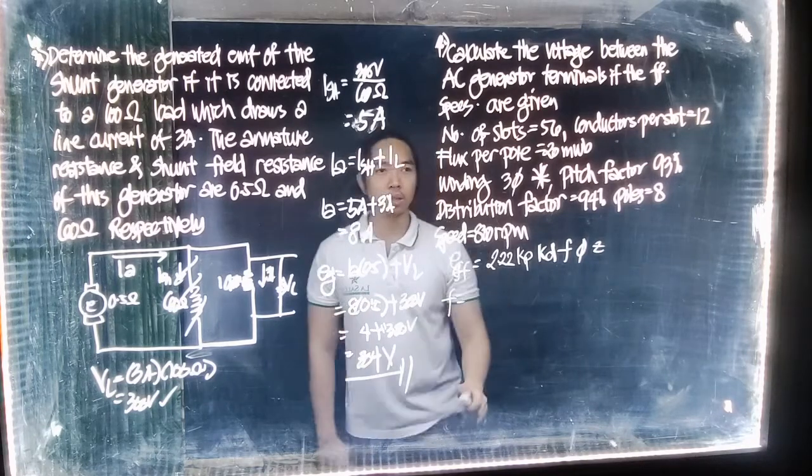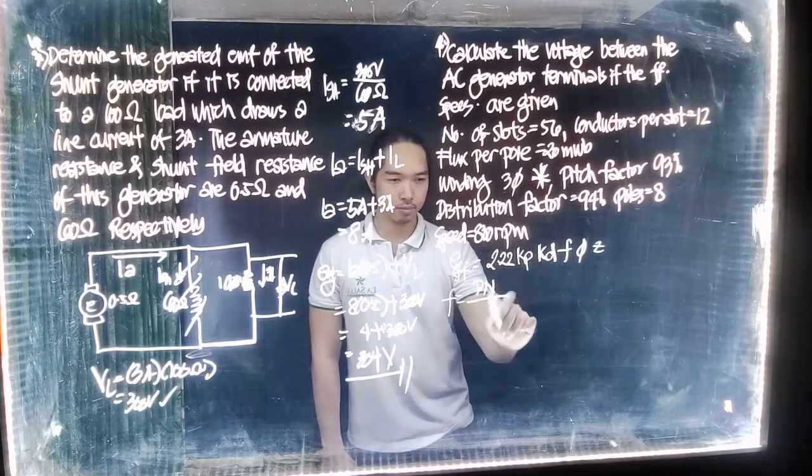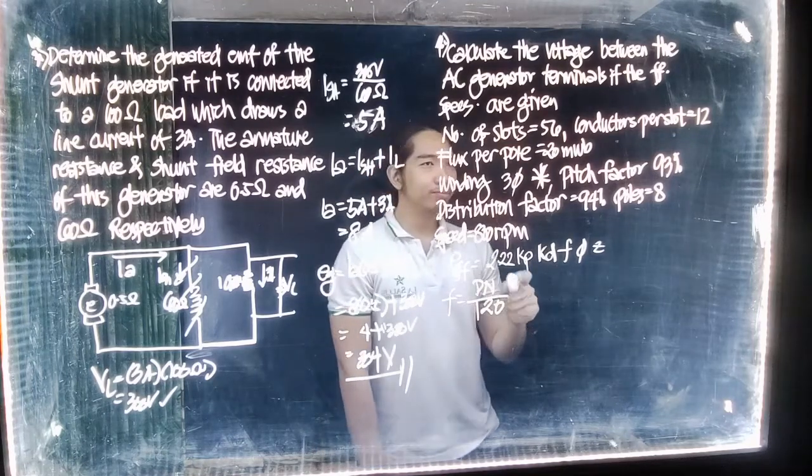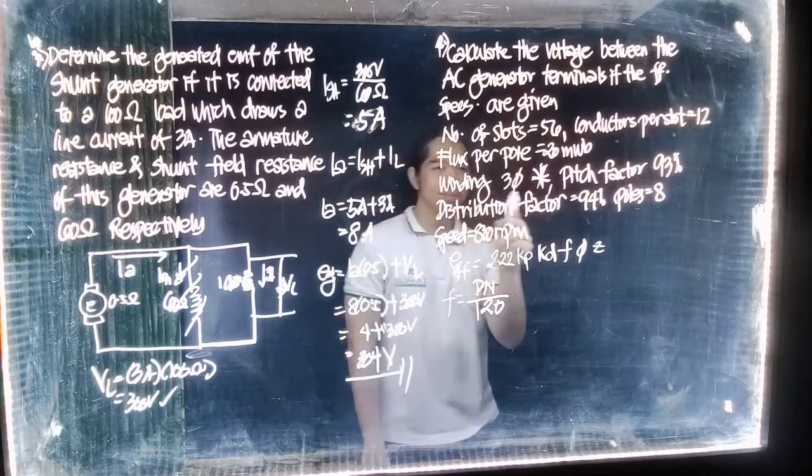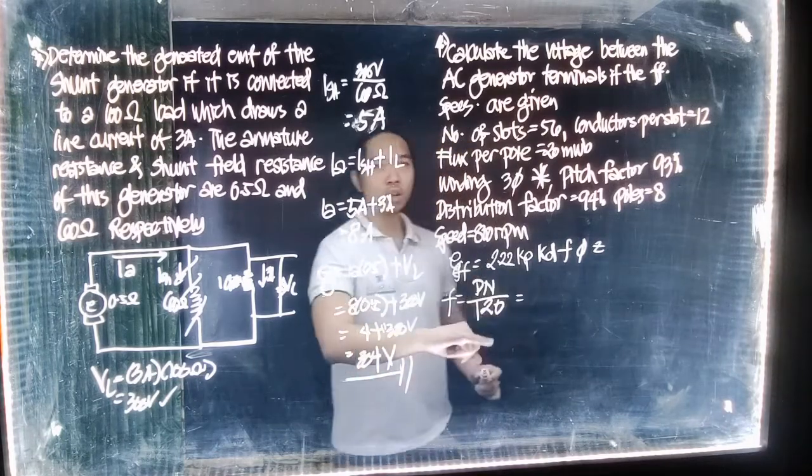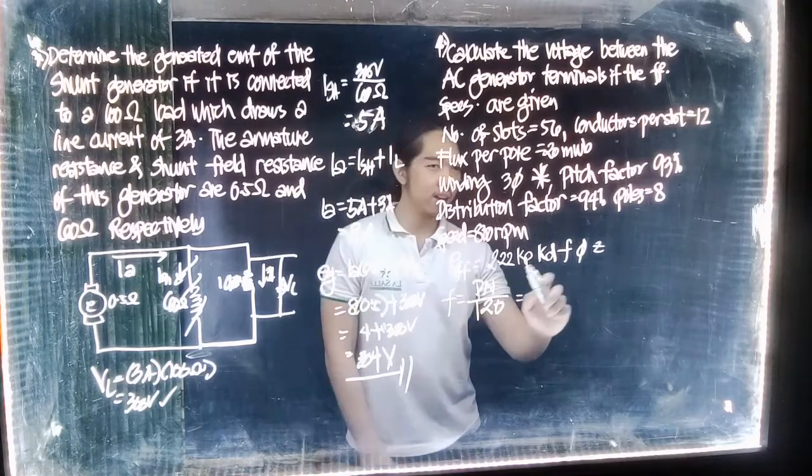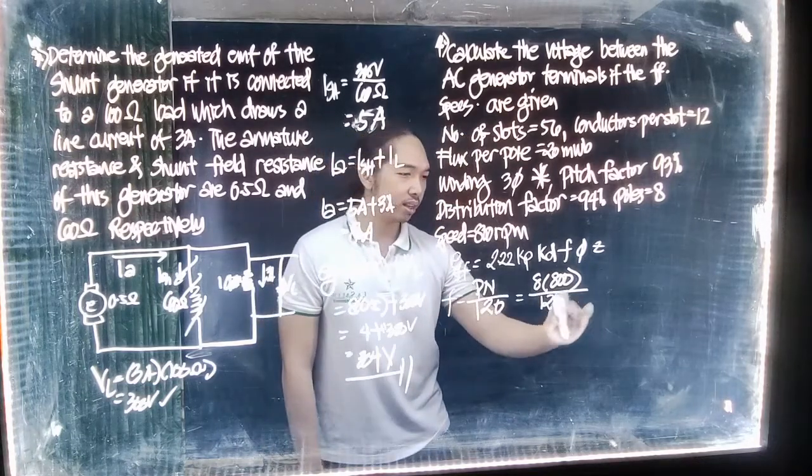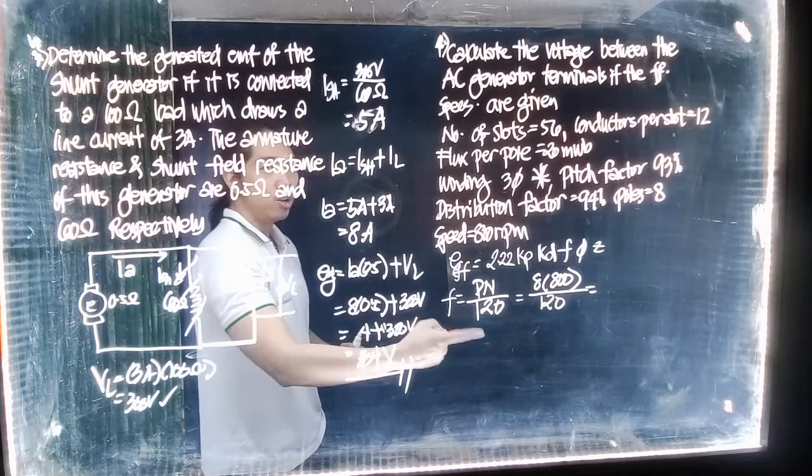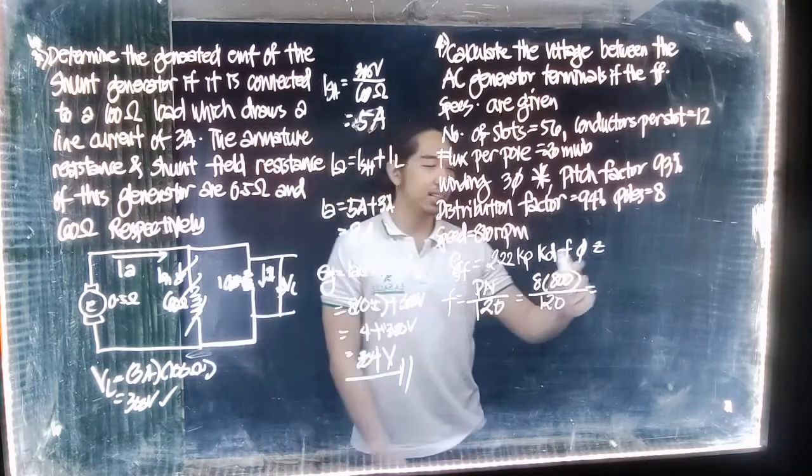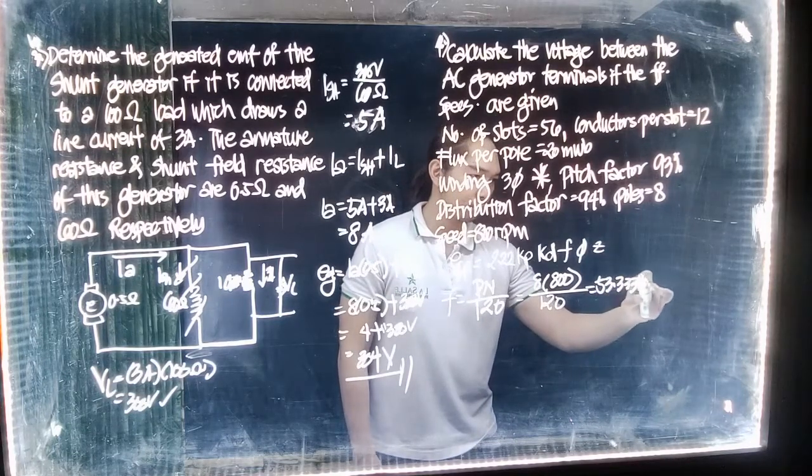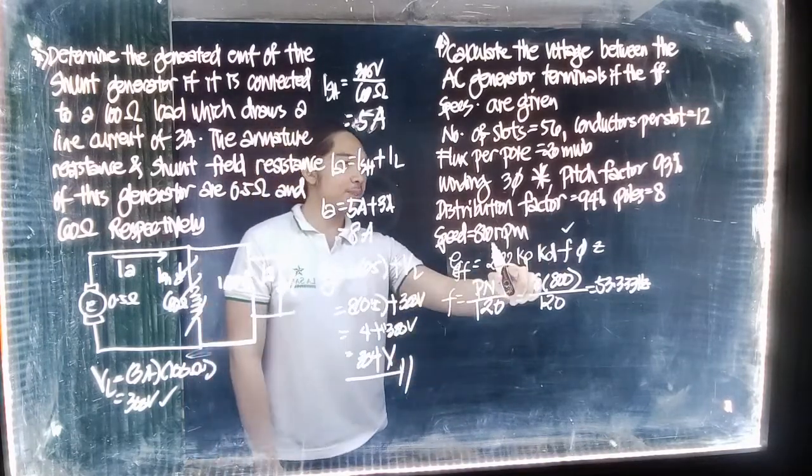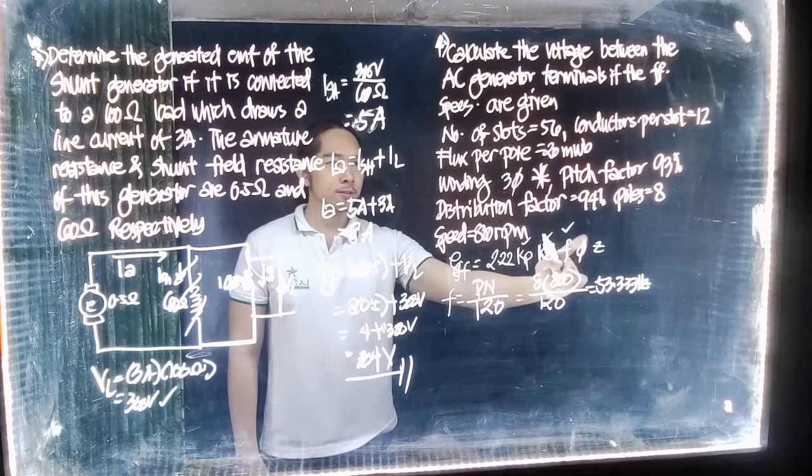To solve the frequency, we're going to use another formula. The frequency is equal to P times N divided by 120, where P is the poles and N is the armature speed. If we're going to plug in all of the values here, we have 8 poles times 800 divided by 120. If you input this in your calculator, you can calculate the frequency as 53.333 Hertz.